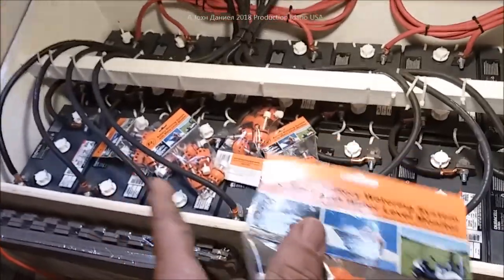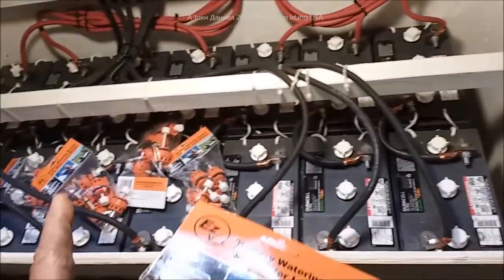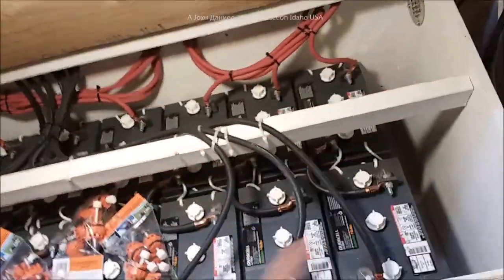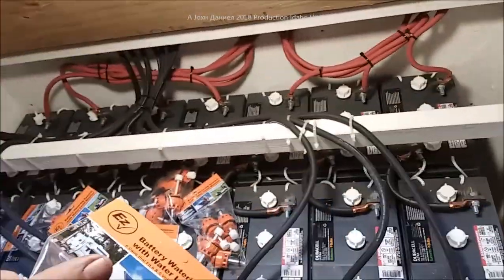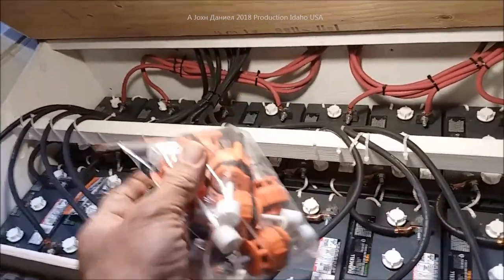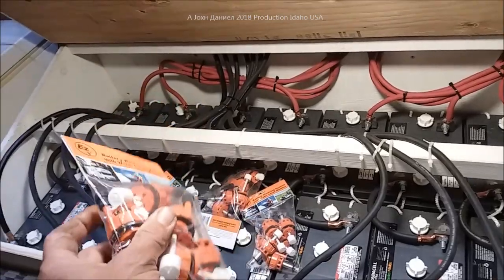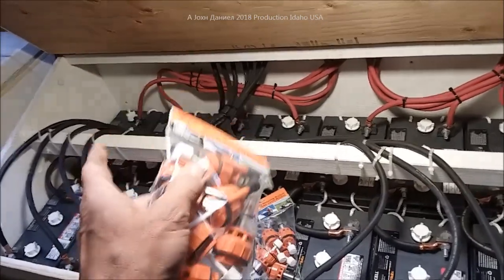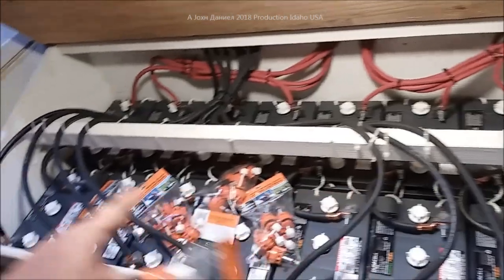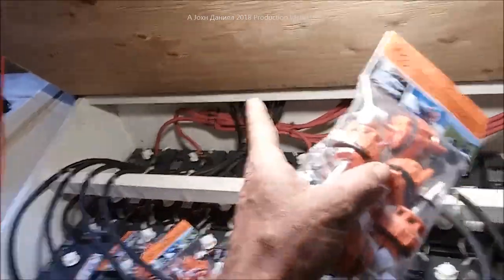This is my balanced battery system — every wire is identical in length so they pull equally. People say you don't need to do that, just bounce the connections around, but what I've seen is end batteries go dry, batteries bulge, and cells fail. I've installed over 70 solar panel setups and about 50 wind turbines in the last eight years, and that string method is as dumb as hell. It's worth spending the extra 50 bucks to do this right.